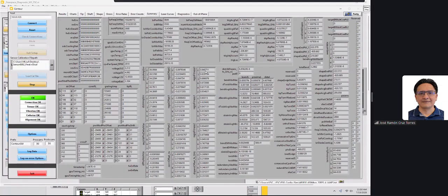That's basically the registration fitness. It tells you how well the current readings are fitting to the expected reading from the calibration file. And sometimes you'll see that the registration fitness is really low and the registration offsets are really high, even though you can clearly see that you have gratings and everything.